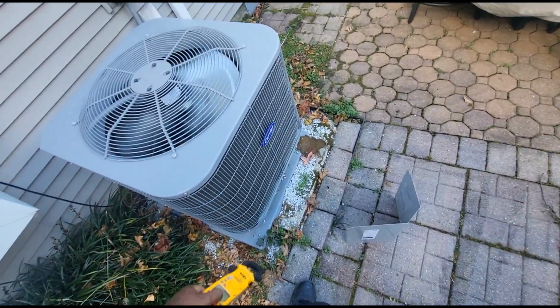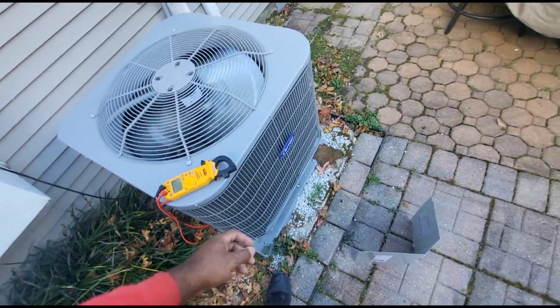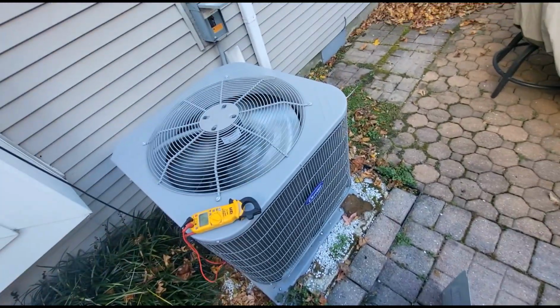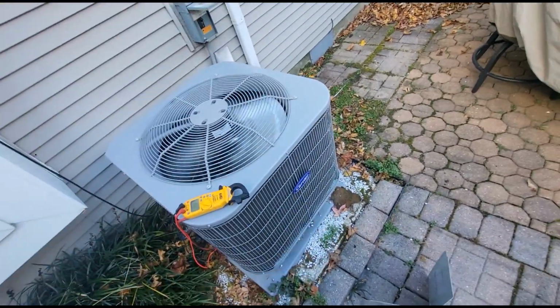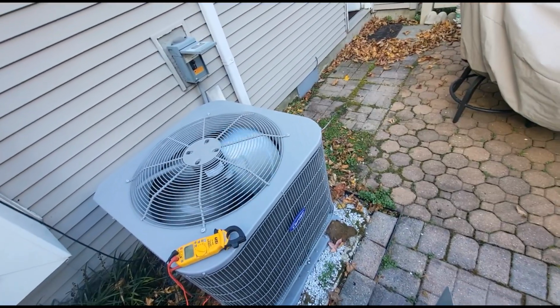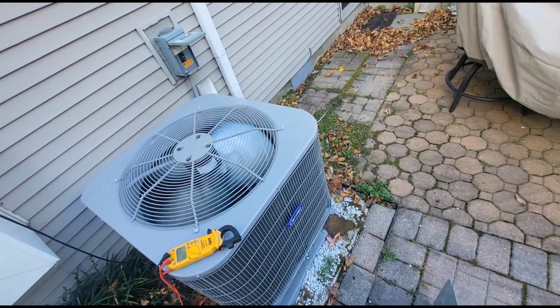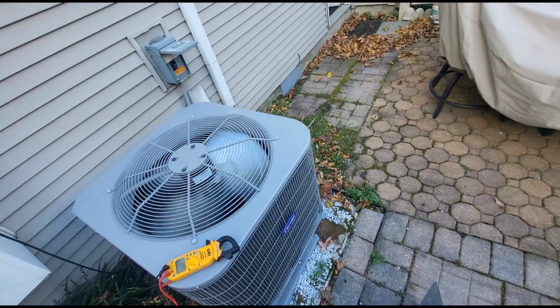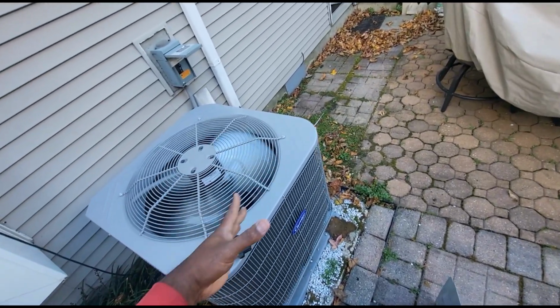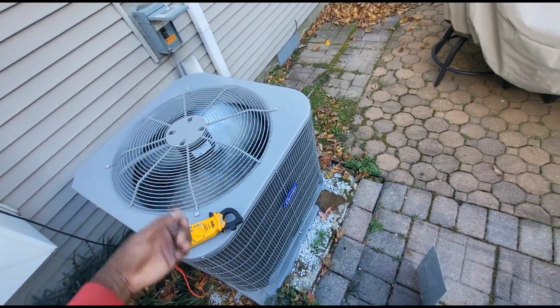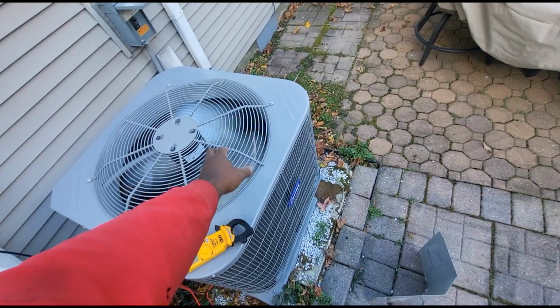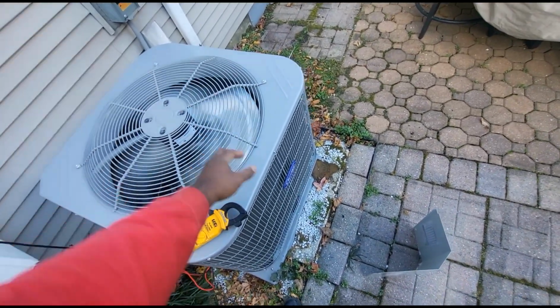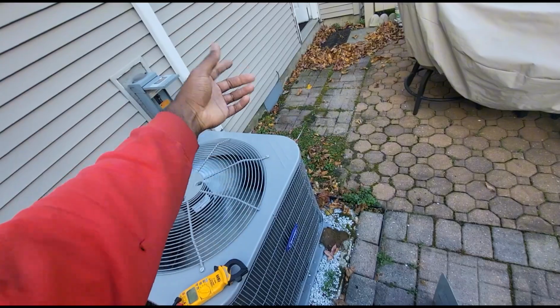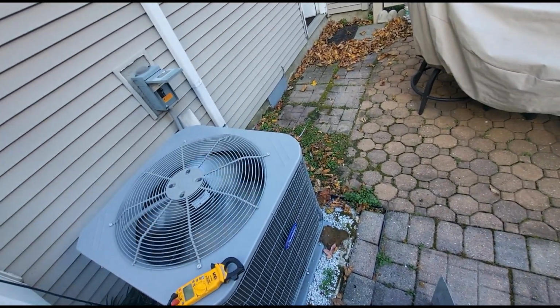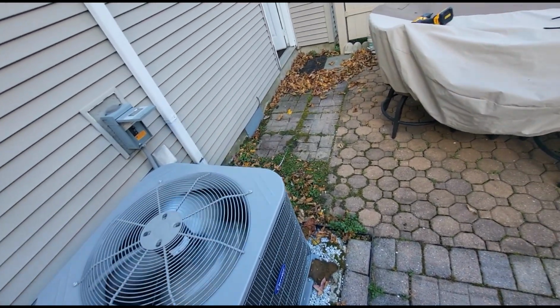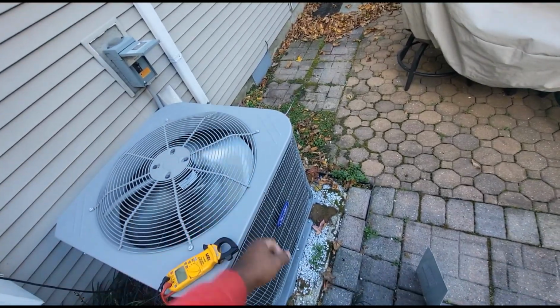He has about 4 or 5 heat pumps. The customer called me. He goes, yeah, I got an error code on my ecobee thermostat. It says that my auxiliary heat is running for an extended amount of time. And guys, with ecobee, that's one thing you need to acclimate yourselves with, Wi-Fi thermostats. Wi-Fi thermostats are smart thermostats, so it measures runtime of your primary heat source, meaning your heat pump, and it measures the runtime of your auxiliary or your backup heat. This customer had a dual fuel setup. He had a gas furnace inside and he had a heat pump outside.